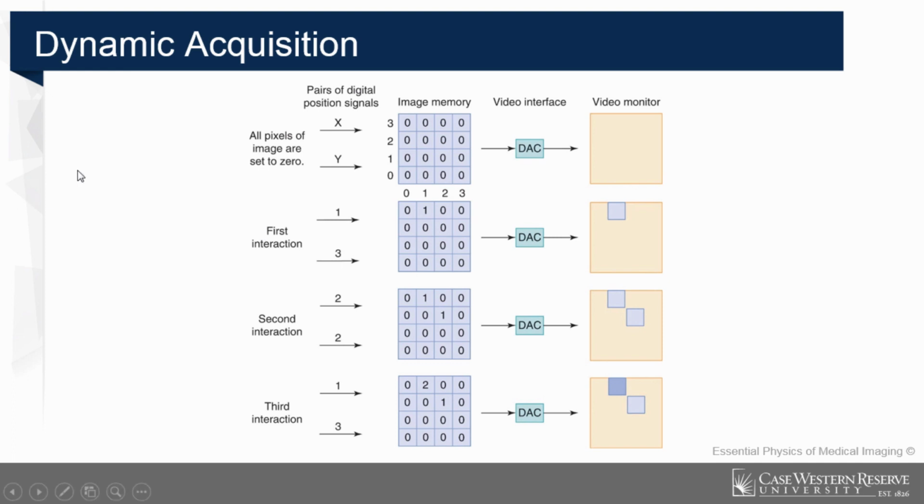So here I should have shown you a dynamic image of the acquisition on the screen, but instead this is a schematic diagram. Let's go through this. So this is what you have. When the first photon comes in, it interacts at a certain position. Then you calculate the center of gravity to locate x and y. The position is here. The separate channel will show you the energy of the gamma photon.